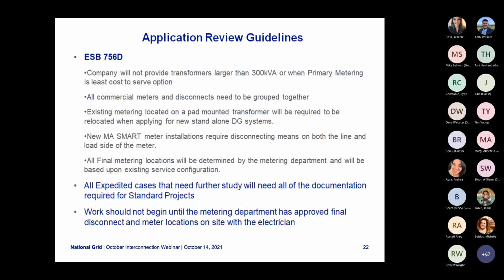All commercial meters and disconnects need to be grouped together. Existing metering location on a pad-mounted transformer will be required to be relocated when applying for new standalone DG systems. New MA smart meter installations require disconnecting means on both the line and load side of the meter. And then all final metering locations will be determined by the metering department and will be based upon existing service configurations.